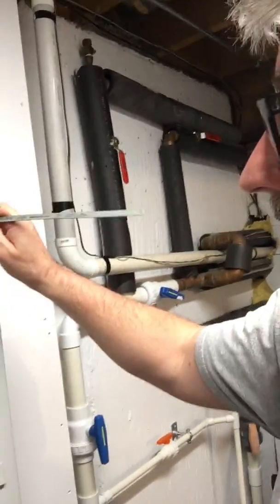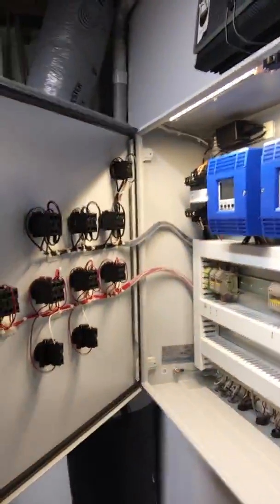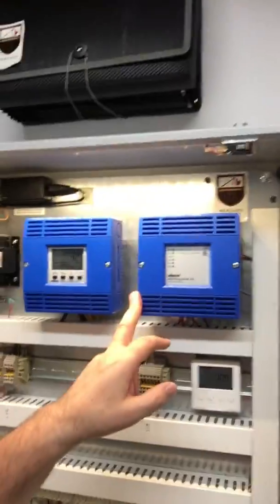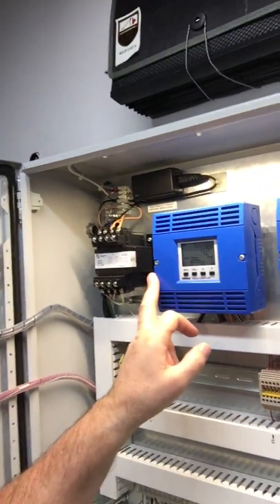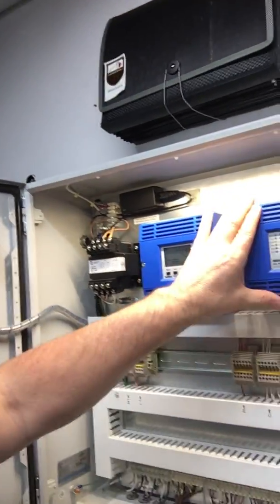So anyways, let's open. Of course, this is the key, right? Everybody has a key for your control panels. In this case, it's a hacksaw blade. Okay, so there it is. I love this. One of the things I like about this is that when Pete built this panel, he put a light in there, so as soon as you open it up, the light comes on, which is an awesome feature. There's the set point control for the swimming pool. There's the zone control relays, and then all of the reset controls and set points for the domestic water and the boiler plant.